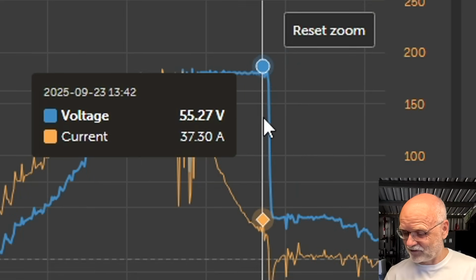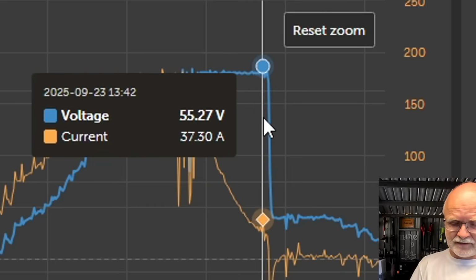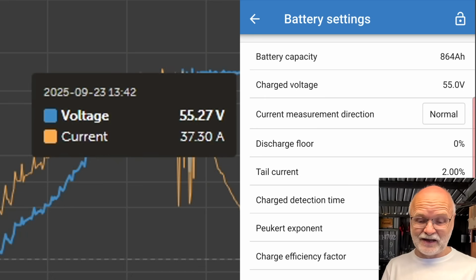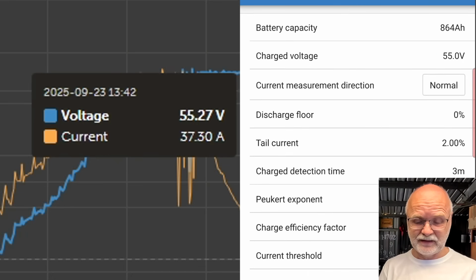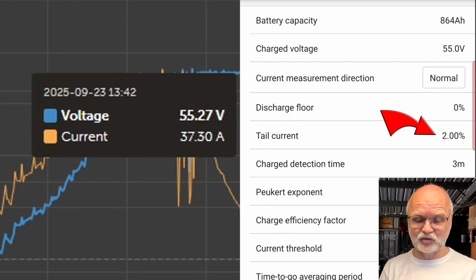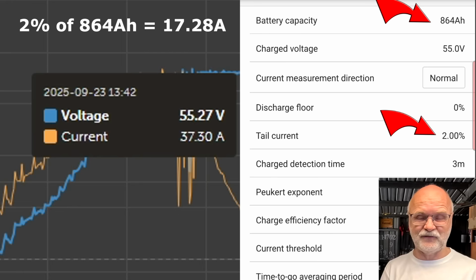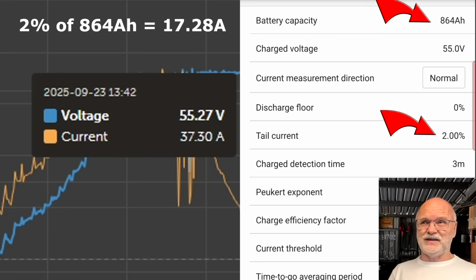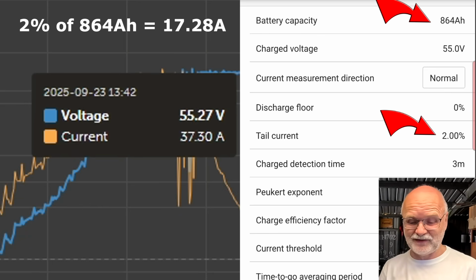We have set the Smart Shunt to reset to 100% at 55 volts. Tail current is 2%, so 2% of 864 is around 17.5 amps, and we were still at 37, so far over this tail current.